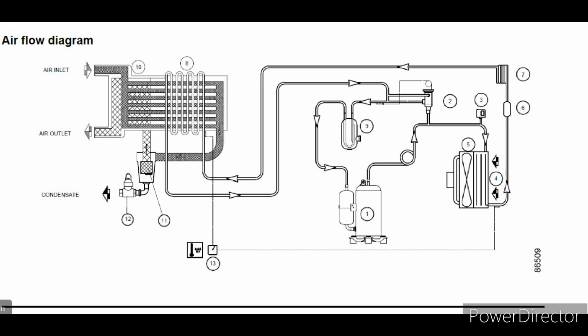Compressed air enters the heat exchanger and is cooled by the outgoing cold dried air. Water in the air starts to condense. Then the air flows through the heat exchanger evaporator where the refrigerant evaporates. This causes the air to cool further, close to the evaporating temperature of the refrigerant. More water in the air condenses. The cold air flows through the separator where all the condensate gets out of the air. The condensate is automatically drained through the outlet. The outgoing cold dried air flows through the heat exchanger where it is warmed up by the incoming compressed air. So this is the airflow diagram.